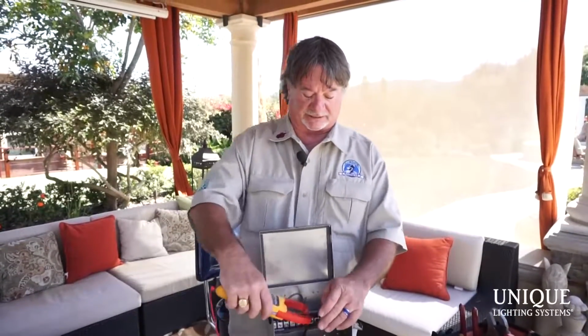Here's what happens: the homeowner picks up the phone and calls me, and I ask, did you touch the system? Of course, every time they say no. So I go out to the field, I grab Mr. Amp Probe, because Mr. Amp Probe never lies. I put it around the wire, and what do you know? It says 2.5. Now I know somebody has messed with me, because I look at my label and the label said it was 0.3.